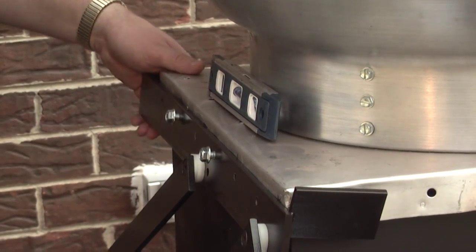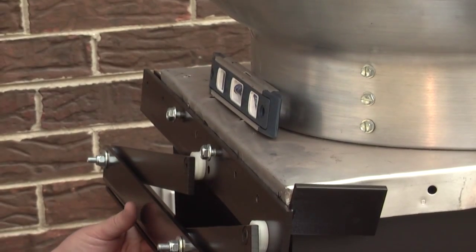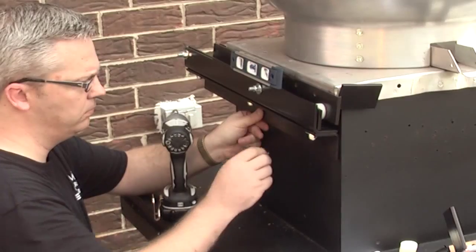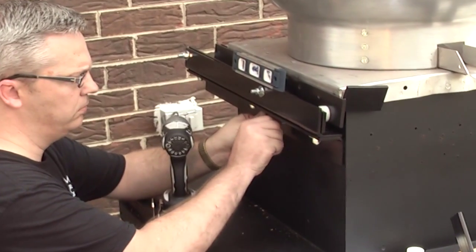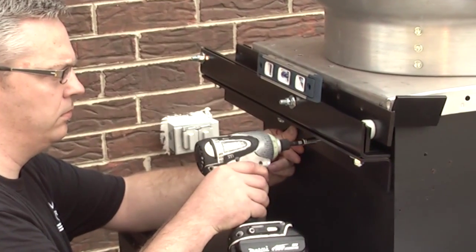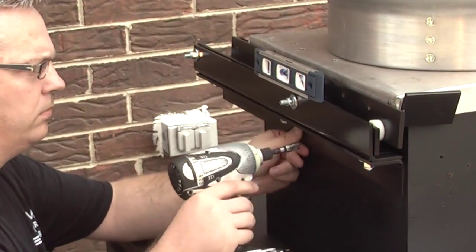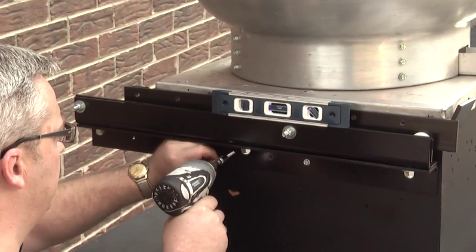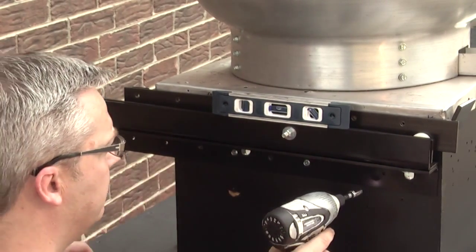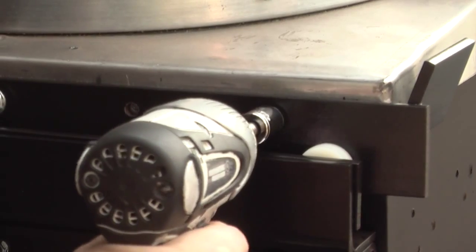Now slide the lower arm all the way up and make sure it's level before screwing it to the fan curb. Fasten the first screw to the right of center. Re-check your level and fasten the second screw left of center. Then add another bolt closest to the curb rest to hold the hinge securely in place.